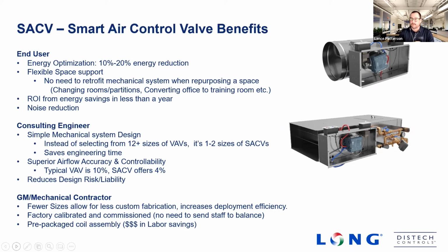Because we're able to achieve lower velocities and lower static, the noise reduction is a big factor for an end user. We've all been in those buildings where you'll hear the ductwork shaking and you'll hear physically the airflow going through some of that duct. So that noise is decreased. From a consulting engineering standpoint though, the noise reduction is another big one because we don't necessarily need that sound abatement anymore designed in the system. So the design gets simplified.